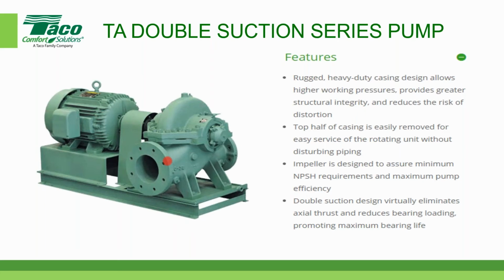And because of that double suction into the impeller, the axial thrust is quite reduced, so the longevity of the bearings should be a lot longer than with the base-mounted pumps.